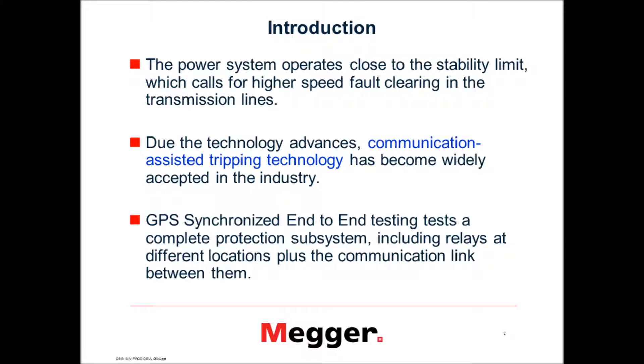Power systems are operating very close to their stability limits, and that calls for very high-speed fault clearing in the transmission lines. Due to technology advancements, communication-assisted tripping technology has become widely accepted in the industry. GPS synchronized end-to-end tests test the complete protection subsystems, including the communication links between the relays.